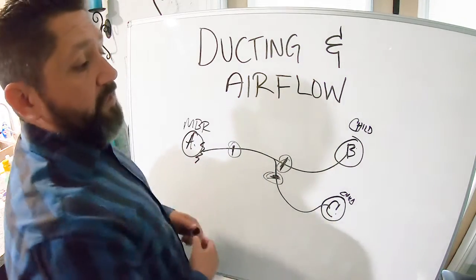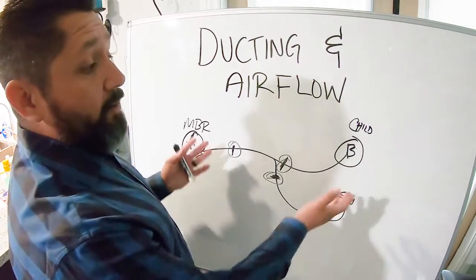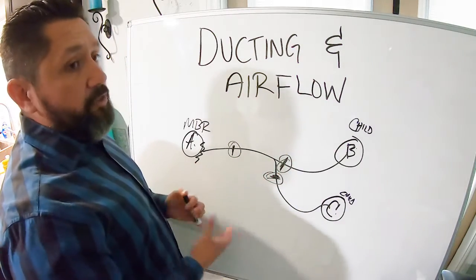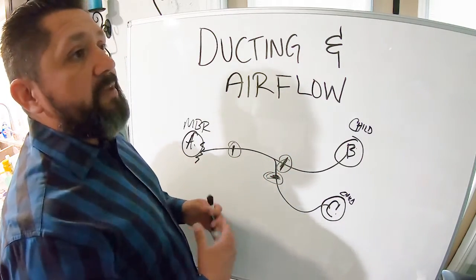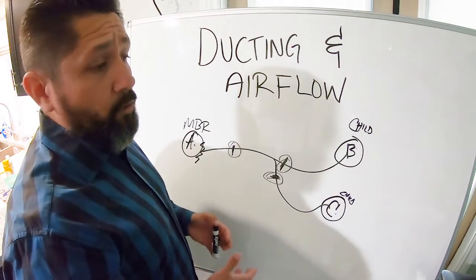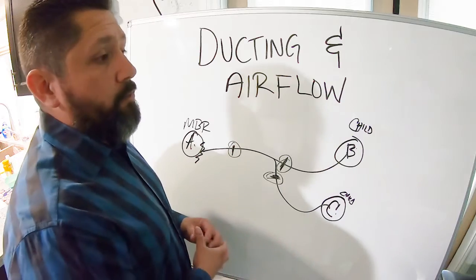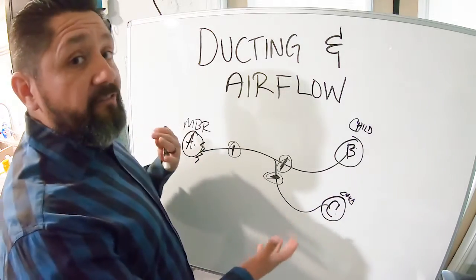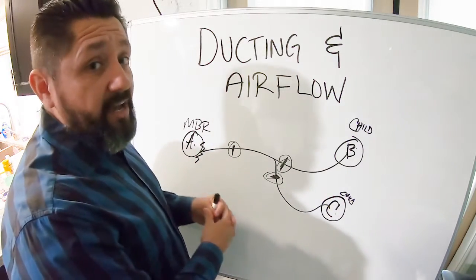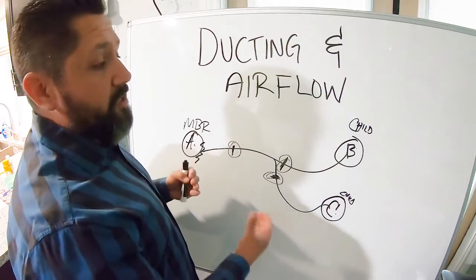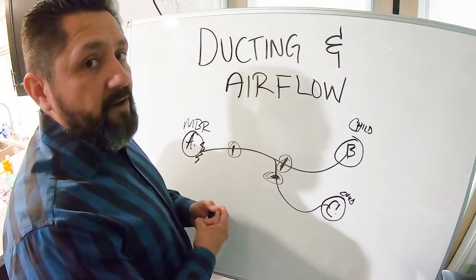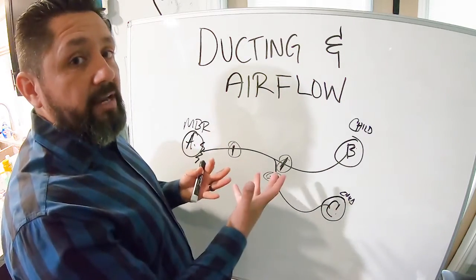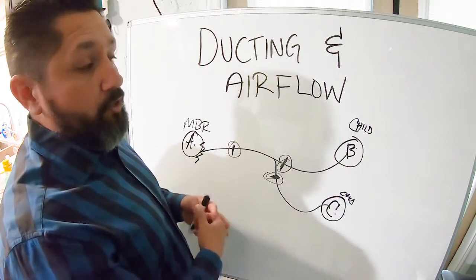Airflow—if you want to change how much airflow goes or where it goes to, that's when you have to go ahead and add these things into the system. The other thing you could do as well is maybe the heater or the blower is too small for the home and it's not supplying where it needs to. Say if the homeowner did a room addition, they now opened up square footage into their home where the unit was never designed to feed that much square footage. You're going to automatically drop the amount of airflow you got by adding a room addition and not upgrading the blower to that system. You're now going to starve it basically.